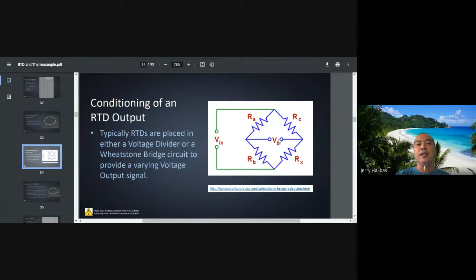Okay, so we go now to the different wirings of the RTD. There are 2 wires, 3 wires, and 4 wires for an RTD. But among the three, it is the 3-wire that is the most common. Okay, what's the most common?